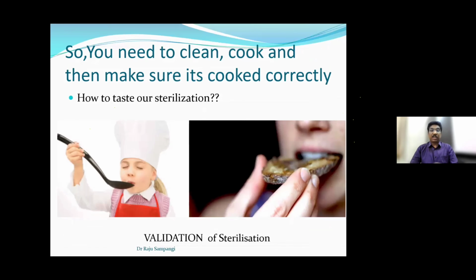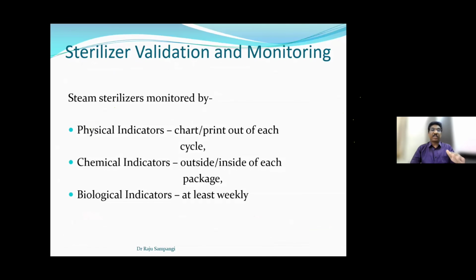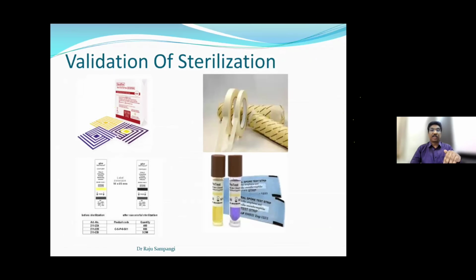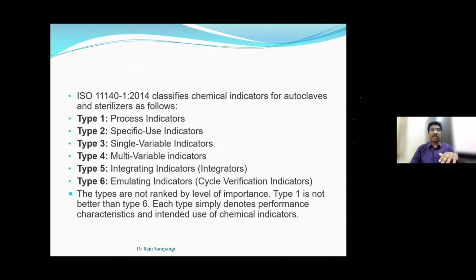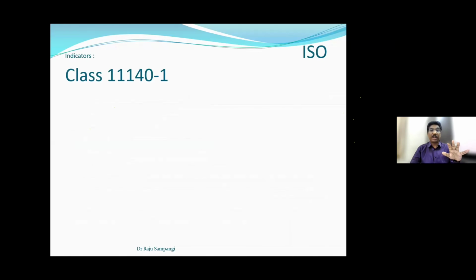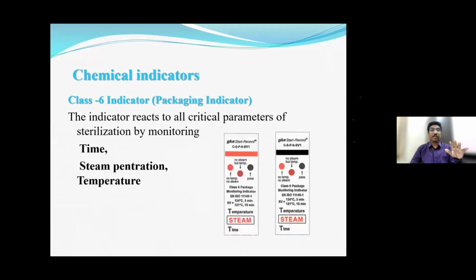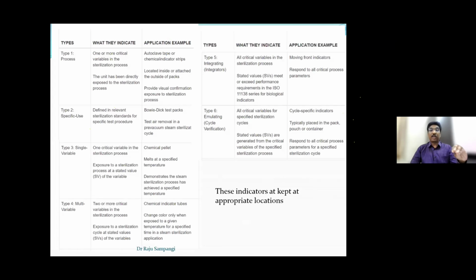The validation of the steam sterilization is just like tasting. You have to use physical indicators, chemical indicators, and biological indicators. I think the other talk will be covering this in detail. I'll just go through it. So there are various classes of indicators, and it's important to understand these are not in order of higher, it doesn't mean the type 1 is better than type 6. What it exactly means is these indicators are for a specific purpose that we are using. And we need to keep these indicators for appropriate function.